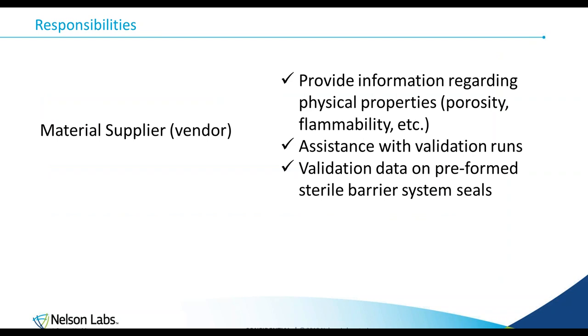As far as responsibility, when you're designing packaging for any kind of product, there's the material supplier and there's your company. So what is the material supplier responsible for? They have to provide you information regarding any kind of physical properties, such as porosity, flammability, and things of that nature. They can assist you with validations, and they have to provide you validation data on preformed sterile barrier systems.